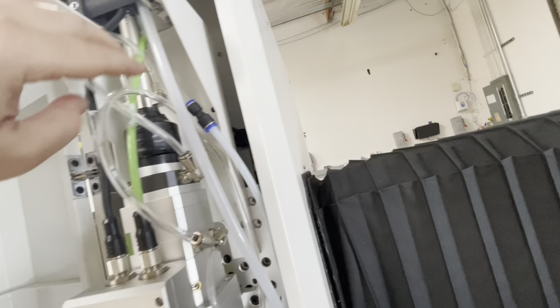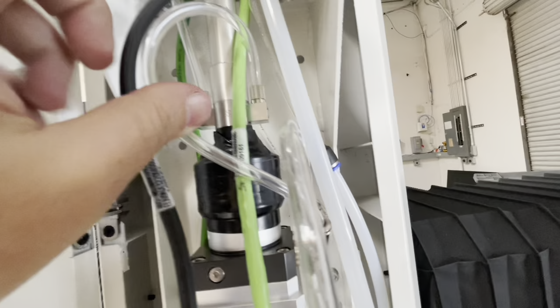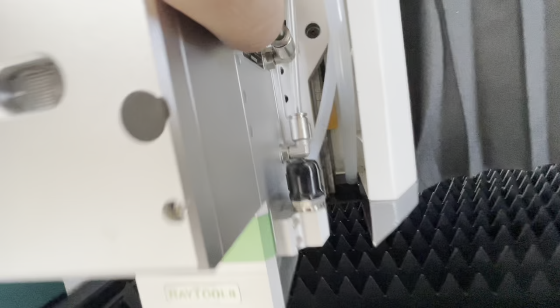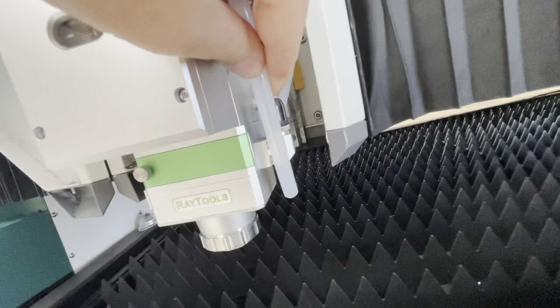Other than that, the rest is just water and gas. Basically you have water coming in at the entry point here, then it exits on this side and comes down and enters back there, then exits and comes down again - it's entering and exiting different parts of the head to get coolant flowing. At the bottom it goes back up and out, returning to the chiller. This is the main gas line, which connects there, but we're going to purge it for a little while first before we put it in.